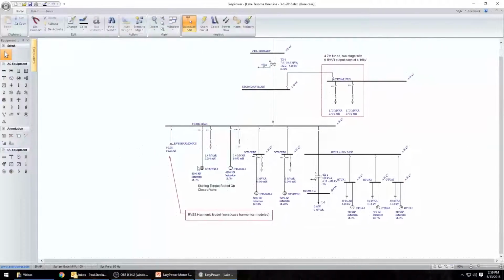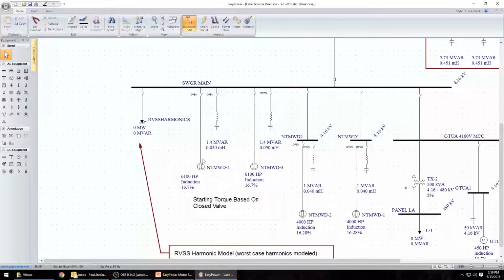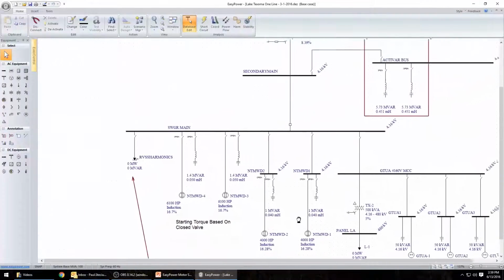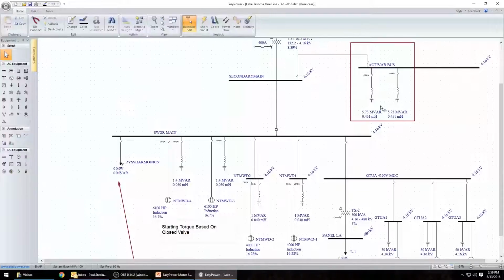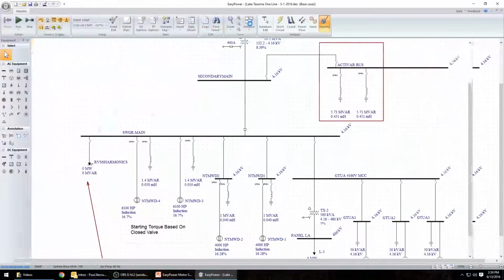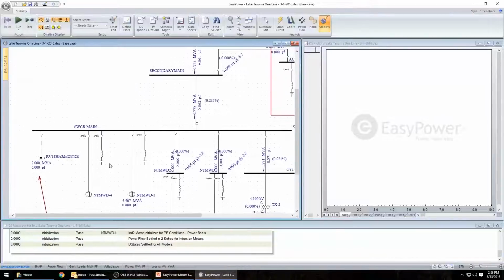So we're going to do a dynamic simulation with the 6,100 horsepower motor here. We're going to have one 6,100 horsepower motor already in operation. The other two 4,000 horsepower motors are offline. We're going to do the first simulation with the actiVAR offline. So I enter into the stability program here. It splits the screen into two, and I've already written some script. And you can view this. I'm going to actually view the script here, but this is the script that we're going to run.